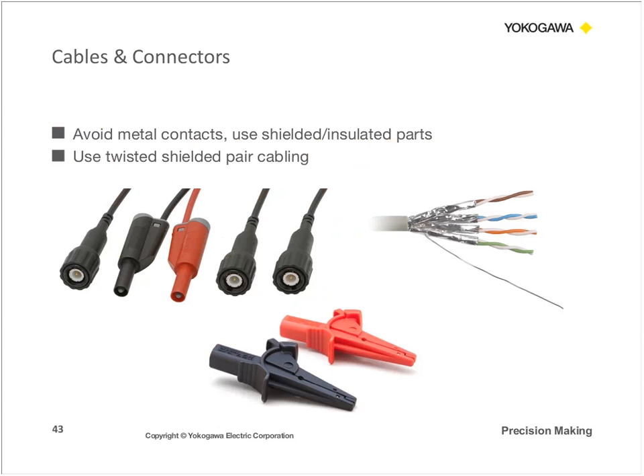When it comes to cables and connectors, some safe practices that you should always promote: avoid metal contacts, always use shielded or insulated parts, and make sure the insulation you select is approved for high voltage. Also, if you're dealing with crosstalk issues, make sure you use a shielded cable pair. It's tempting to run all your wiring through one conduit, but the simple advice is don't do it. It opens up troubles for magnetic coupling or induced voltages caused when you have the cables too close to each other.